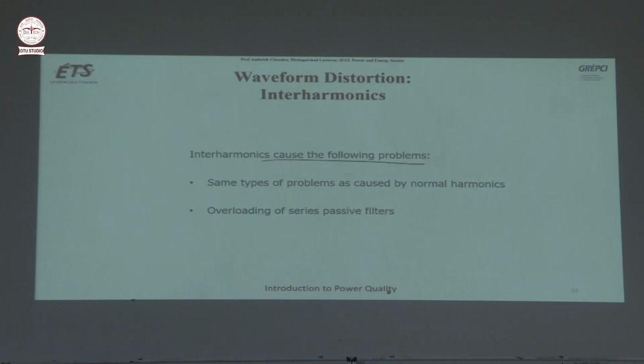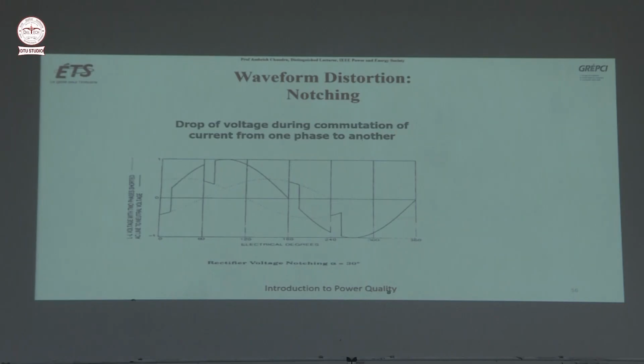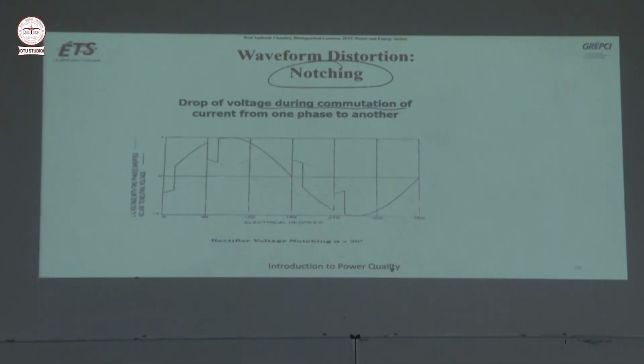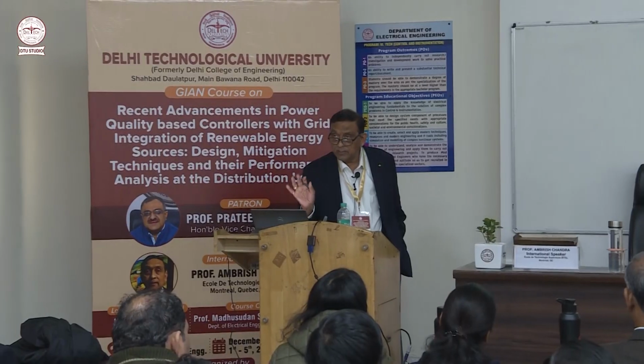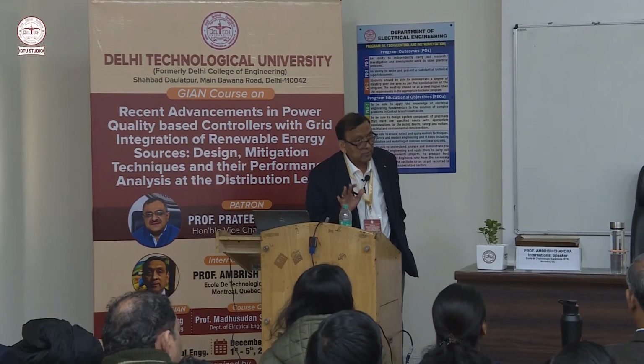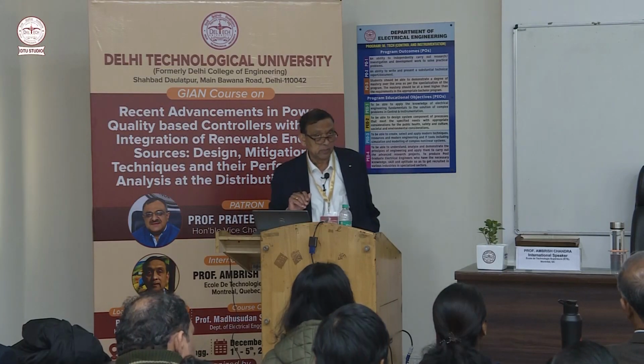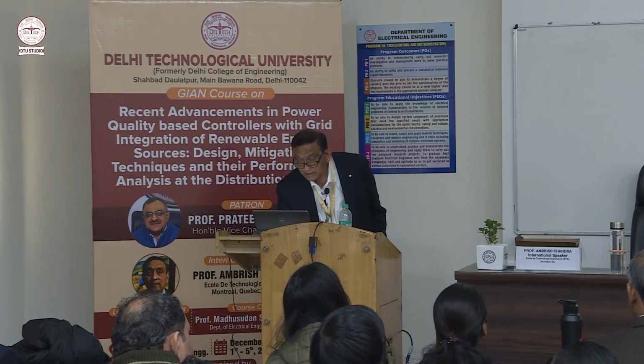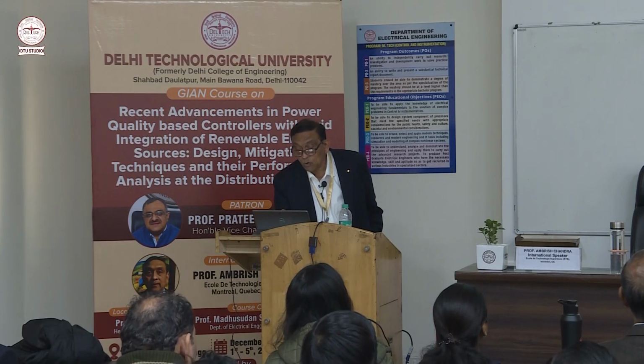Interharmonics cause the following problems. Same type of problems as caused by normal harmonics, overloading of series passive filters. Because it may not be 5, it will be 5.5 or 4.5, but it will overload your passive filter. Drop of voltage during commutation, notching. So earlier I was thinking they are not still talking about notching. This was in 1992. But then I verified in IEEE Standard 519 2014 and even 2022, they are still keeping this thing because thyristors are still very much in use for higher power applications. Okay, so this is the notching caused by commutation overlap.